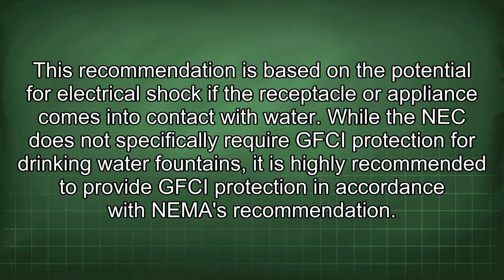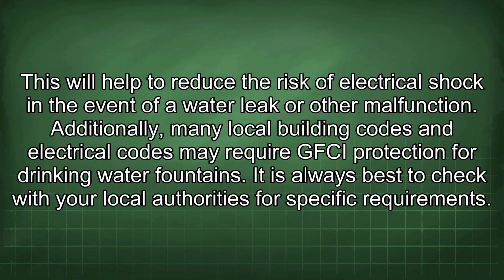While the NEC does not specifically require GFCI protection for drinking water fountains, it is highly recommended to provide GFCI protection in accordance with NEMA's recommendation. This will help to reduce the risk of electrical shock in the event of a water leak or other malfunction. Additionally, many local building codes and electrical codes may require GFCI protection for drinking water fountains. It is always best to check with your local authorities for specific requirements.